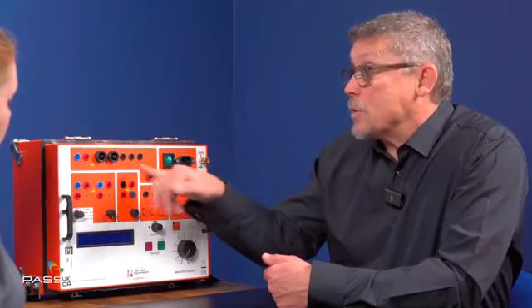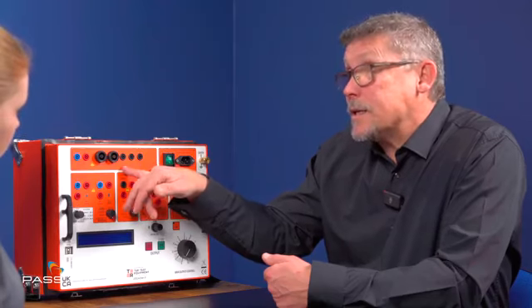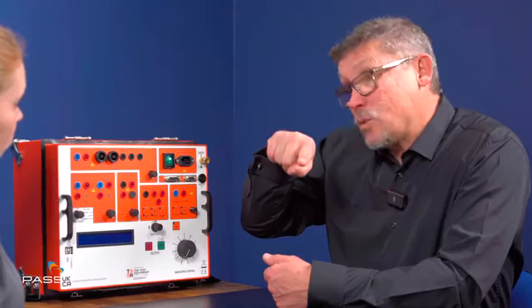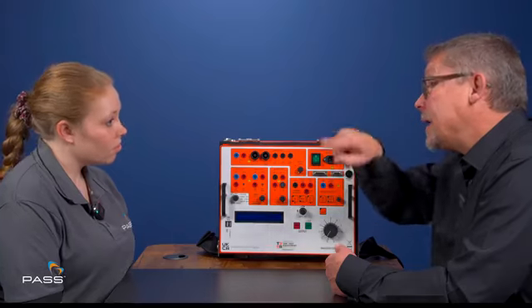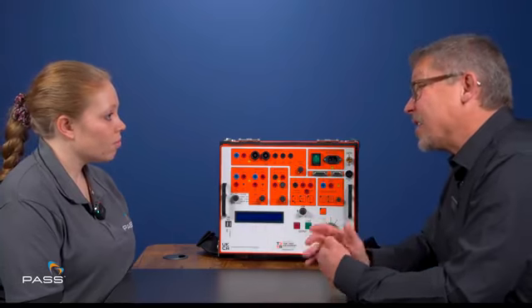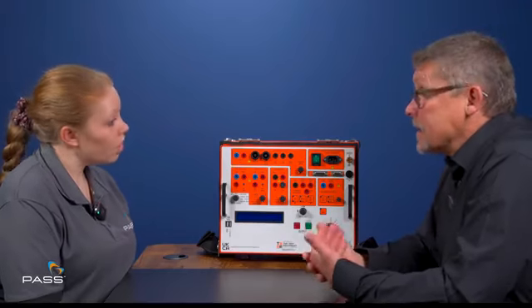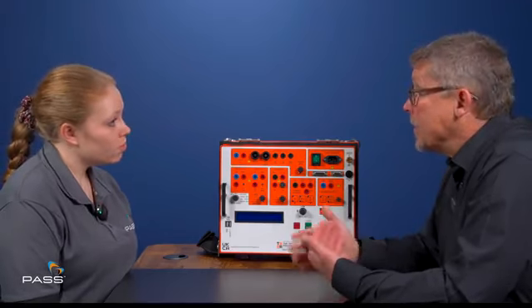One of the things we can actually do that I hadn't even mentioned with this, for example, is we have the ability to do CT saturation tests, i.e. what we do is we input voltage into the CT and we monitor the point at which current flows, and that gives us what we call a knee point graph. And that knee point graph means we can then check the CT for its magnetism. CTs lose magnetism over a period of time. It's one of the many things about this unit.